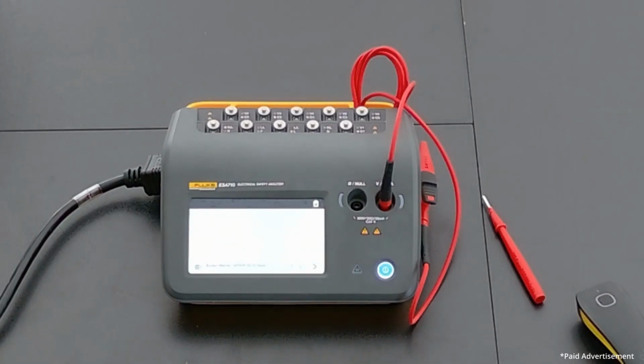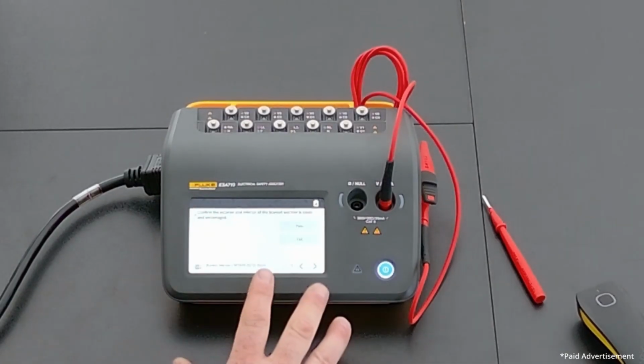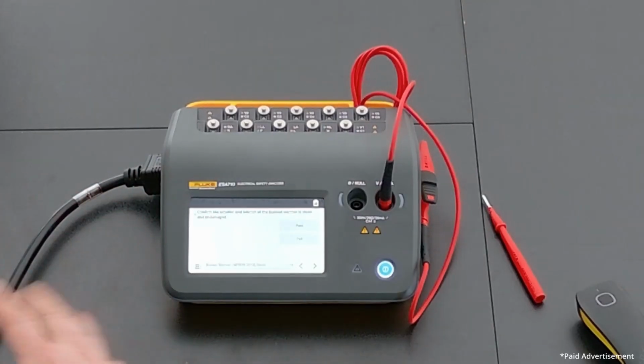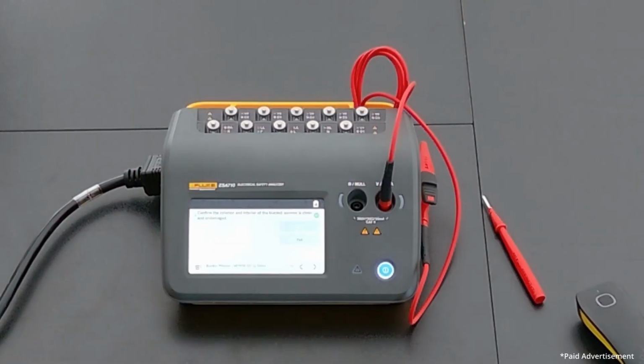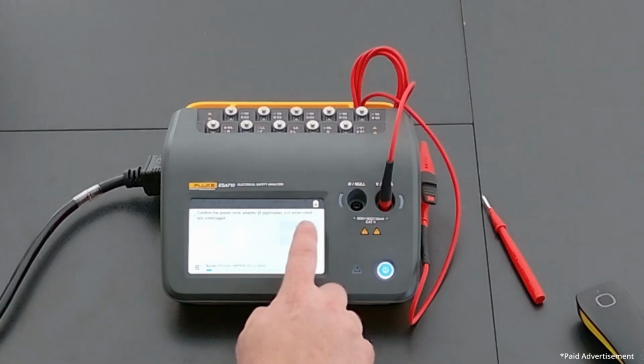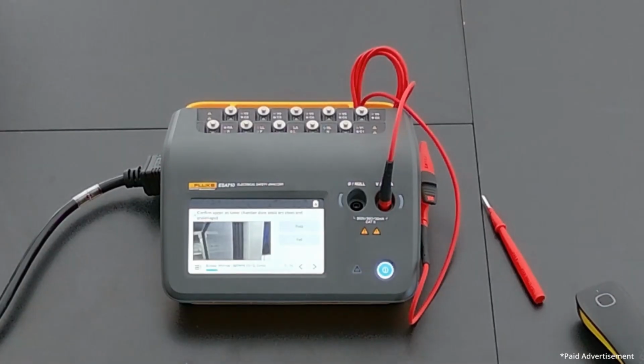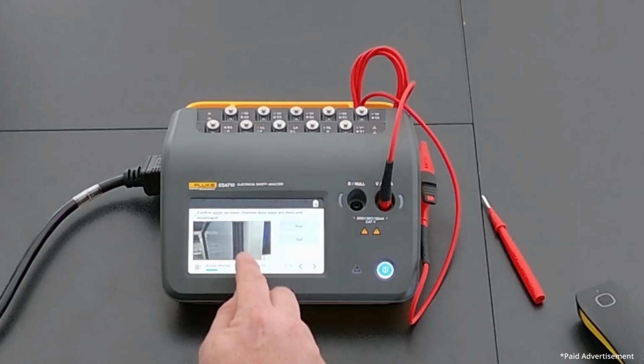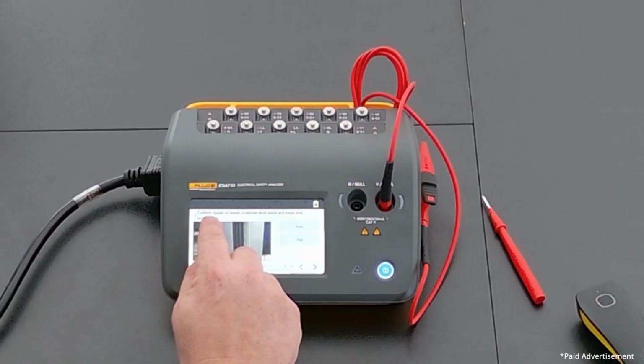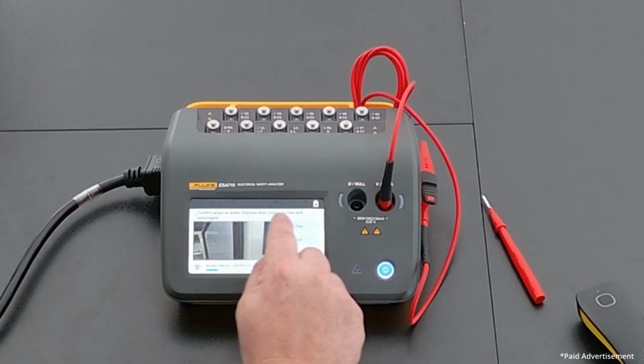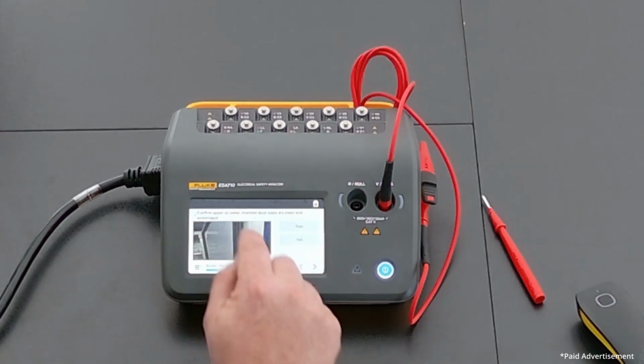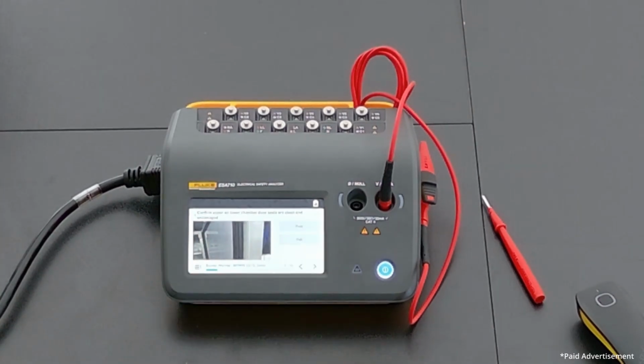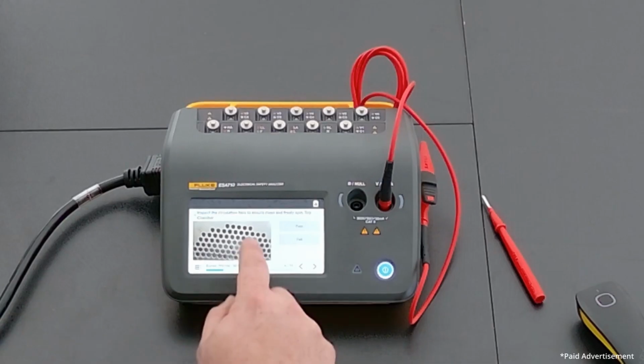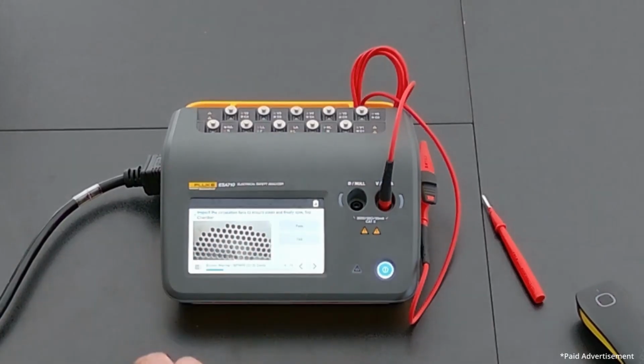So I can push run on this, and now my procedure right out of my CMMS system is at my fingertips, because it's been a while for me, so I might not remember how to do my procedure. So I can read the instructions and give it the pass or fail, and I can do things like embedded pictures. Here's a blanket warmer door showing that I'm supposed to check and confirm the upper and lower chamber door seals are clean and undamaged. Right there's a picture of that door seal. So I'll say that yes, it's clean. And now here's a picture of what I'm supposed to see when I look at my circulator fan.